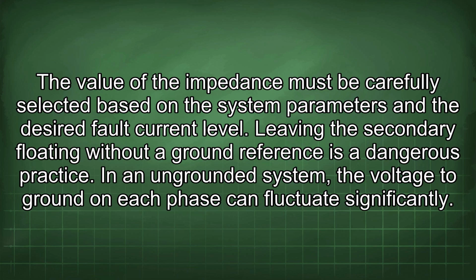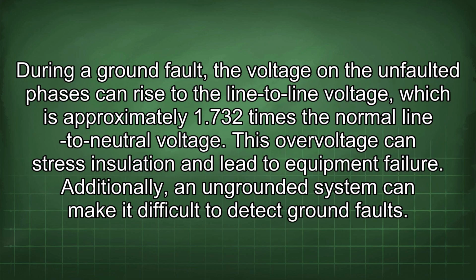Leaving the secondary floating without a ground reference is a dangerous practice. In an ungrounded system, the voltage to ground on each phase can fluctuate significantly. During a ground fault, the voltage on the unfaulted phases can rise to the line-to-line voltage, which is approximately 1.732 times the normal line-to-neutral voltage. This overvoltage can stress insulation and lead to equipment failure.